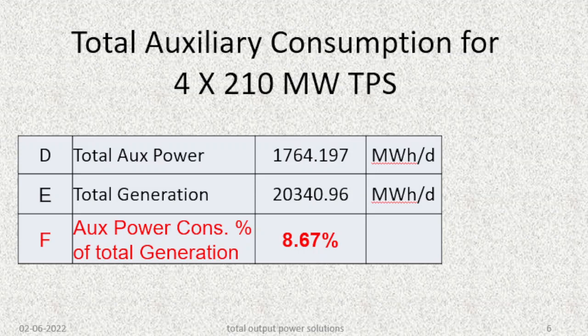The total auxiliary consumption for the whole 4 x 210 MW thermal power station was 1764.197 MWh per day. If all sets run at 210 MW, the total generation would be 20,340.96 MWh per day. The auxiliary consumption works out to approximately 8.67% of total generation.